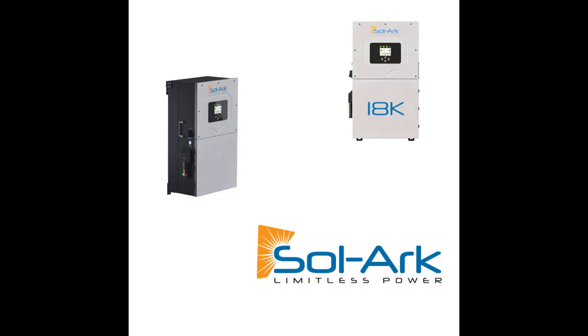Thanks, Mark. So yeah, this is our peak shaving. The basic idea of peak shaving is to offset the peak with battery, but more so that the excess solar that we're producing, that ordinarily would go out to the utility, which nowadays you're hardly getting any kind of payback for solar export, is instead being utilized to drive down the overall utility usage. So you get the benefit of the PV driving down your usage, plus the peak demand and usage of the battery to drive down the peaks, or use it for time of use during the evening hours for those companies or businesses that have extended opening hours. All right, next slide, Mark.